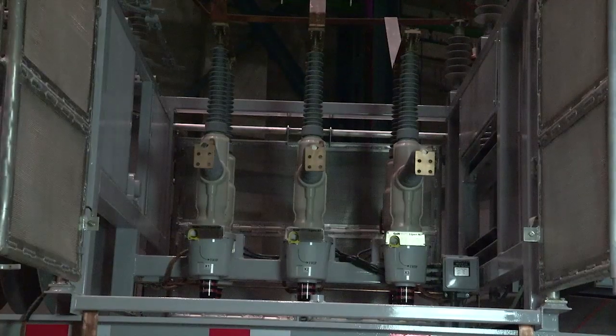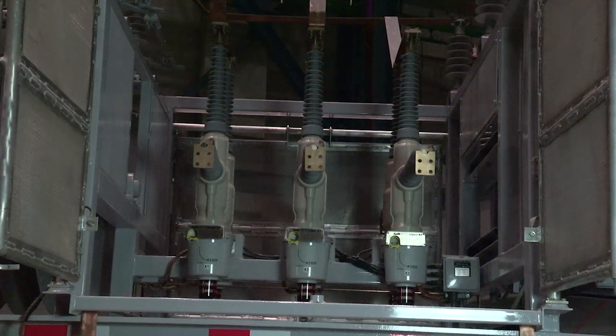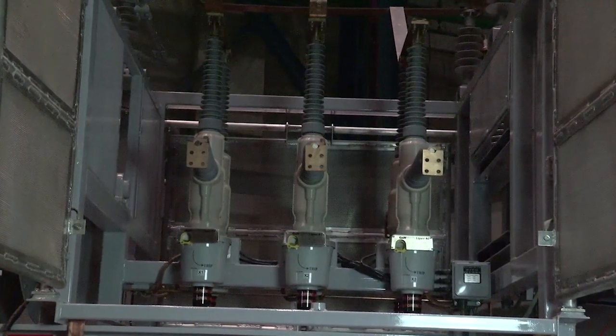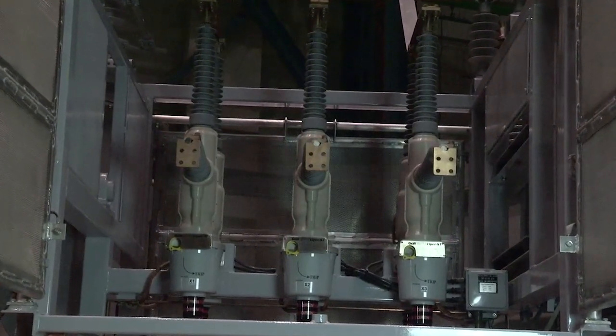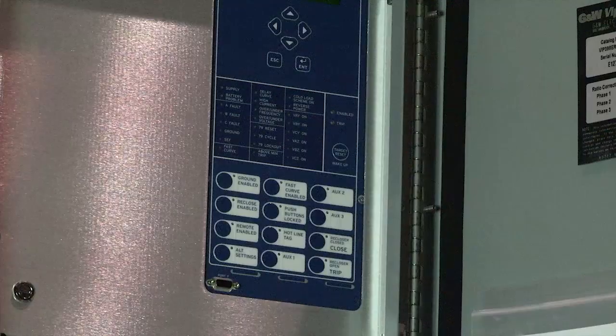G&W Viper reclosers are currently being installed on new and refurbished mobiles. These reclosers are electronically controlled and equipped with vacuum tube interrupters. The normal operation is at 120 volts with a DC battery backup and a solenoid closing coil. Each phase of the recloser has 3 tripping solenoid coils that, when activated, will discharge a spring, allowing the recloser to open.